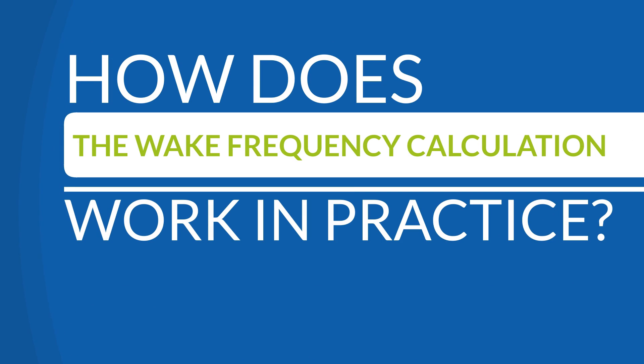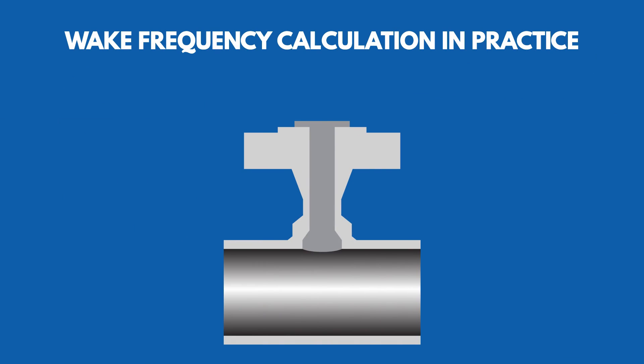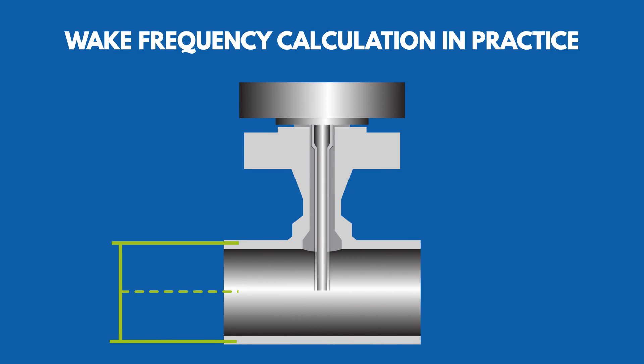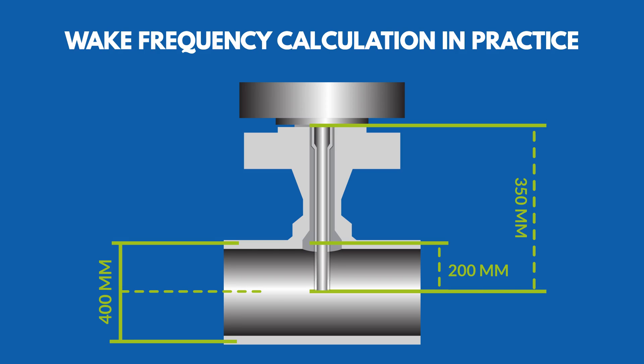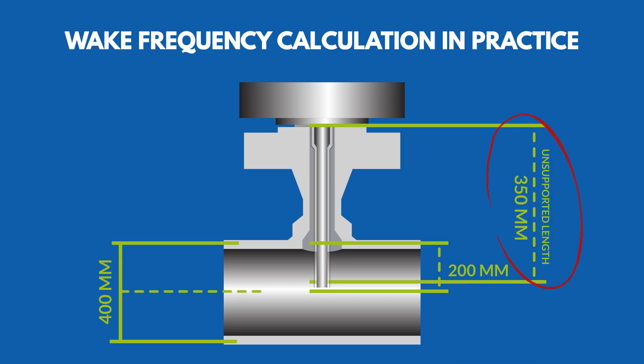So how does the wake frequency calculation work in practice? Let's check an example. An insertion DBB valve with probe must be inserted halfway into a 400 mm diameter pipeline. To achieve that the probe tip is in the middle of the pipeline at 200 mm, the probe length must be 350 mm. This overall length is considered as the unsupported length. After the wake frequency calculation, the result shows that the maximum unsupported length is 300 mm instead of the required 350 mm. In this case, a support collar must be inserted to achieve the length required by the end user.